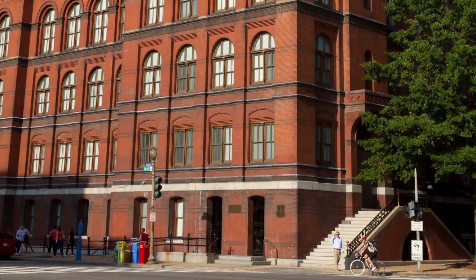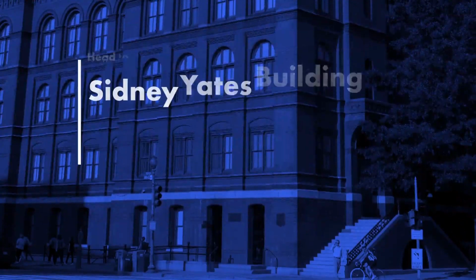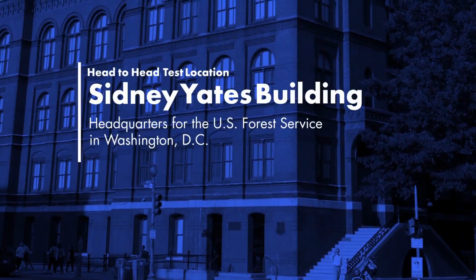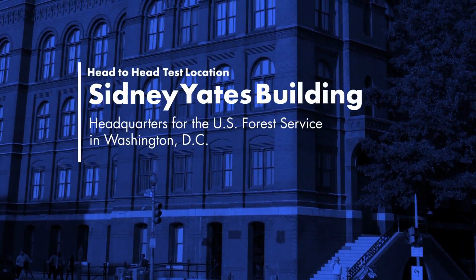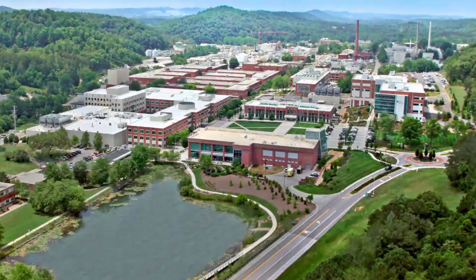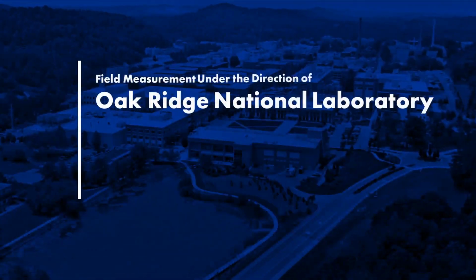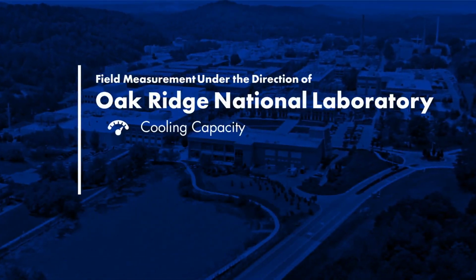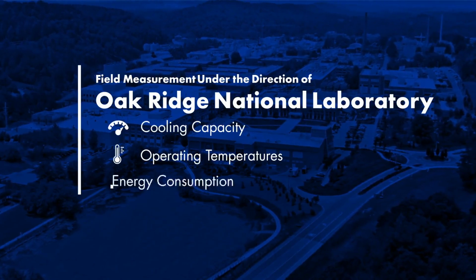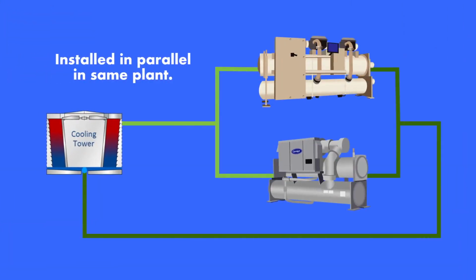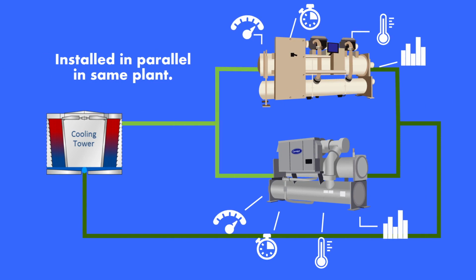These chillers were evaluated in a side-by-side comparison in the Sidney Yates Building, headquarters for the U.S. Forest Service in Washington, D.C. With Oak Ridge National Laboratory direction, instrumentation was installed to measure cooling capacity, operating temperatures, and chiller energy consumption. Both chillers were connected to the same chilled water and condenser water loops, allowing for an objective comparison of operating efficiency, reliability, and sound across a broad range of operating conditions.